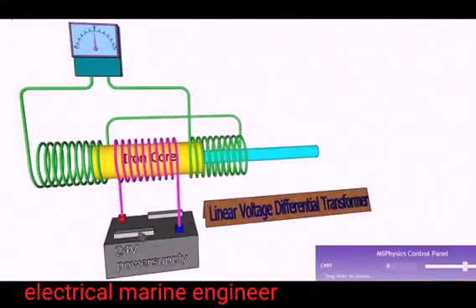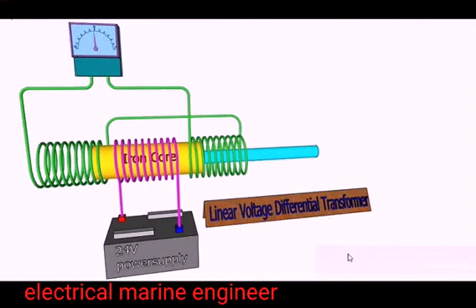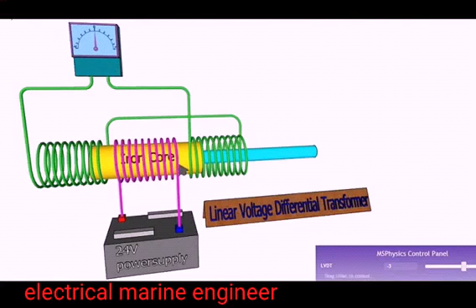And the next one is the LVDT sensor, which stands for linear variable differential transformer. As the name itself says, it is a transformer having a primary and secondary coil. The primary is given a 24 volt supply, and the secondary coils are connected in series, but in reverse manner, as shown in the figure. When you change the spool position, the current passes through this transformer. You can see how the voltage is varying in the meter. Accordingly we can get the position of the main spool. This is actually fitted on the main spool to get the position.